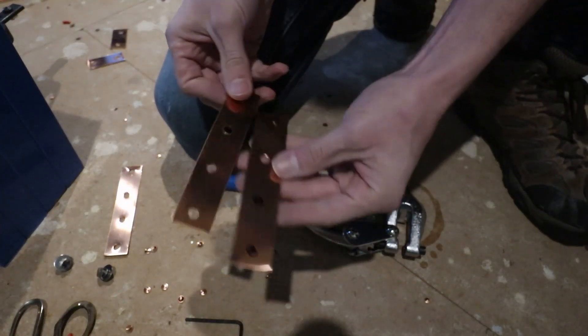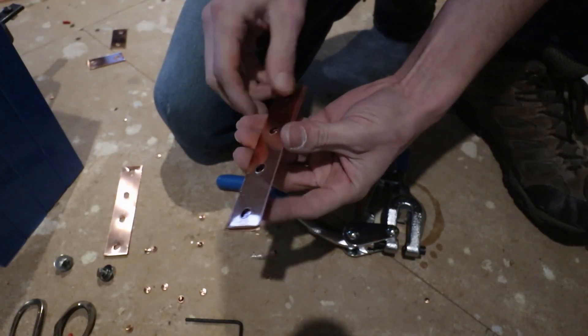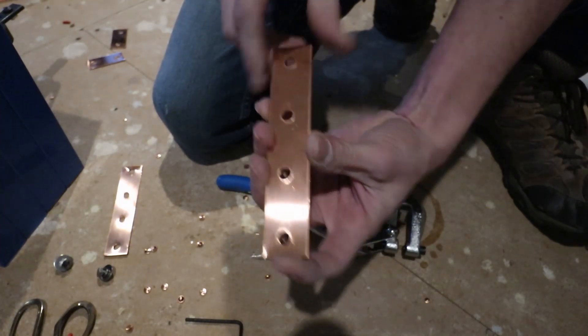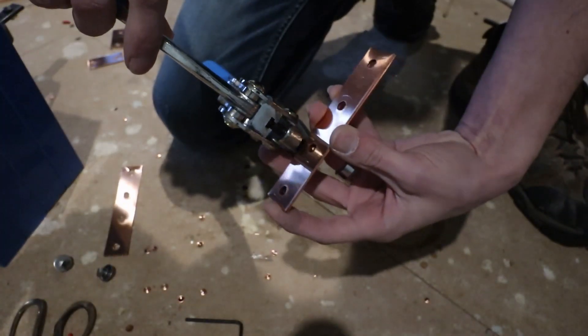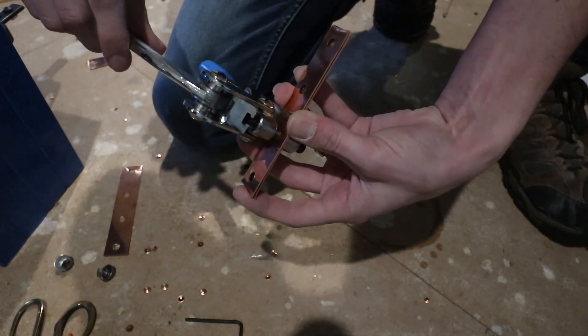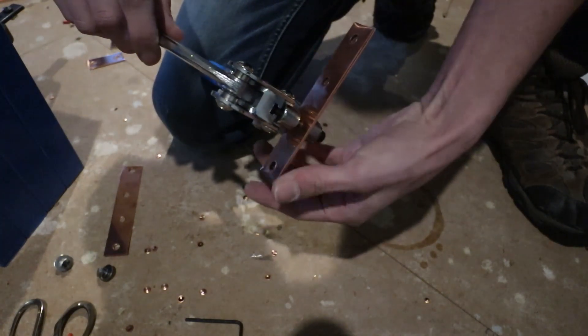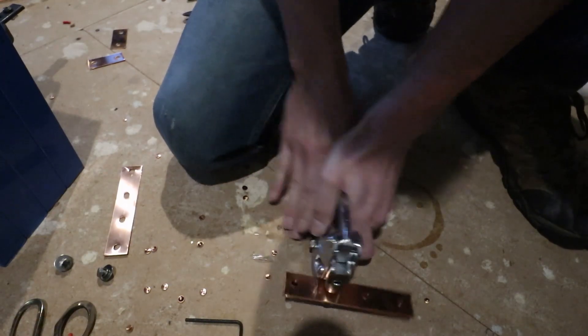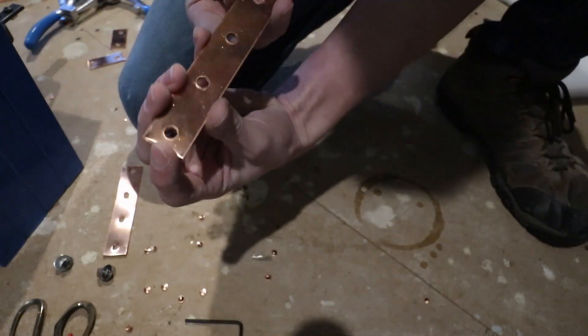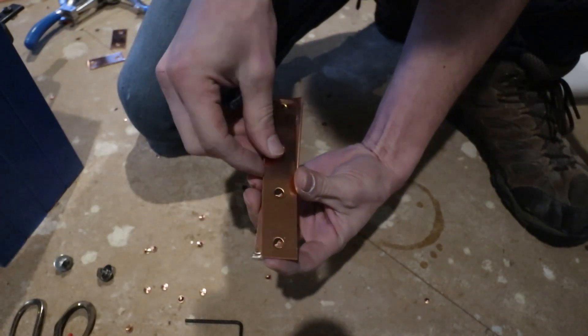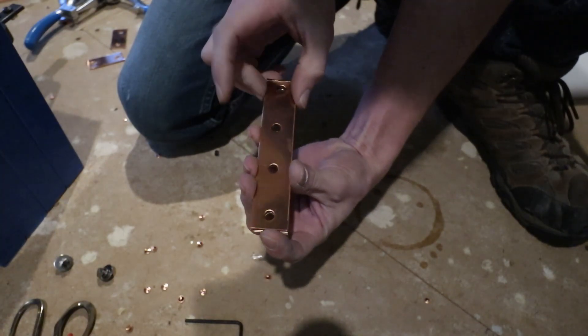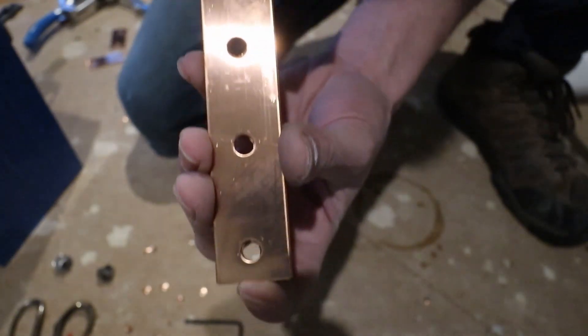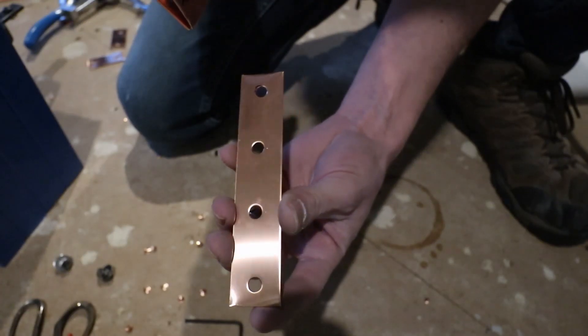Another tip is once you get one bus bar that you like that has the holes in the right place, instead of just marking holes and then punching, you can actually hold the good bus bar on top of the new one and go ahead and punch right through it, which should give you an exact copy of what you want. There we go. Exact copy. Whereas this one I did, I just marked holes and then punched and you can see it's just a tad bit off from the original. You can be real careful and get the original just right. You can use it as a template.